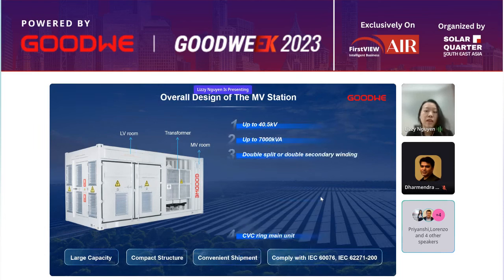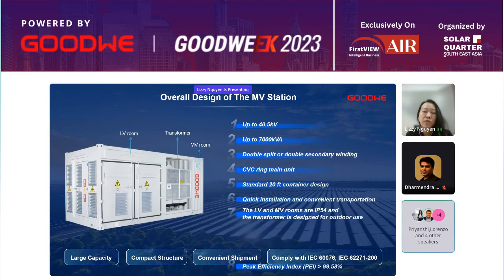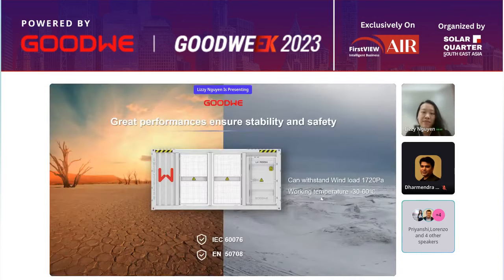Here are some highlights of the MV station: it can go up to 40.5 kilovolt, 7000 kVA, with double split or double secondary winding, CVC ring main unit, and standard 20-foot container design, among others. It can also withstand wind load of 1,720 Pa and working temperatures from negative 30 to 60 degrees Celsius.